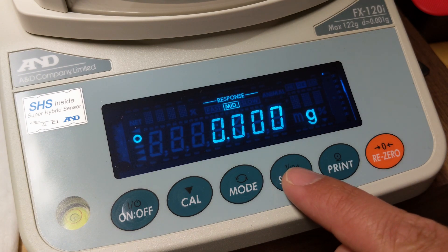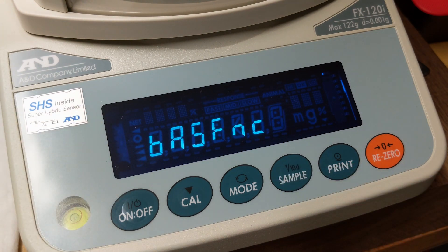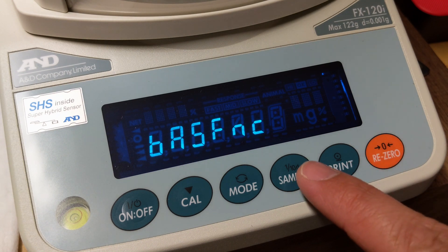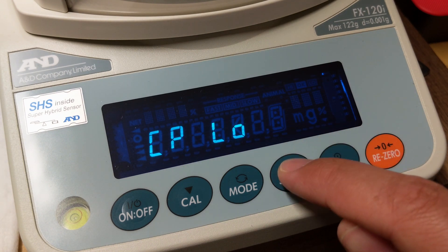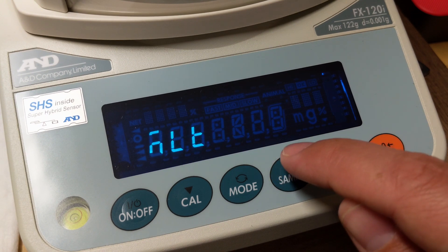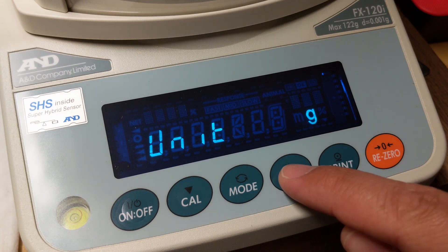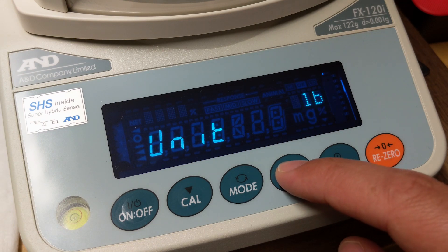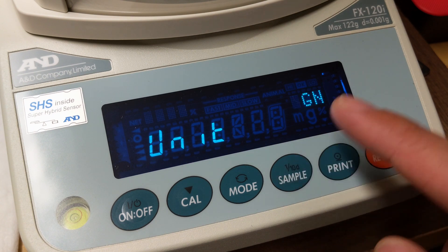Press and hold the sample button. You'll hold it until it says 'basic function.' Now you'll continue to press — not hold, just press — the sample button until it says 'unit.' Once it says unit, you'll press print. Then it'll show grams.